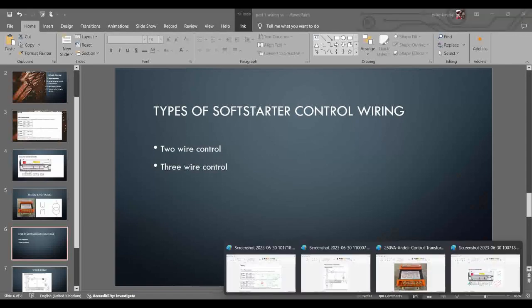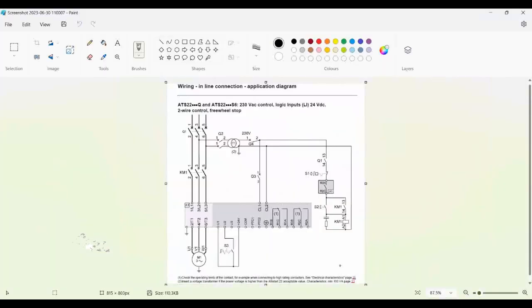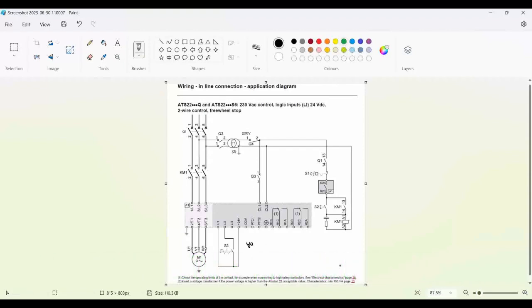Now, let's look at the different methods of wiring the Altistart 22 soft starter. We have the 2-wire control and the 3-wire control configurations. Ensure to check the operating limits of the contact, especially when connecting to high-rating contactors. Insert a voltage transformer if the power voltage exceeds the Altistart 22's acceptable value. The transformer should have a minimum rating of 100 VA. For the two configurations, we will use the selector switch connected to LI2 while looped to 24 volts DC and LI1.